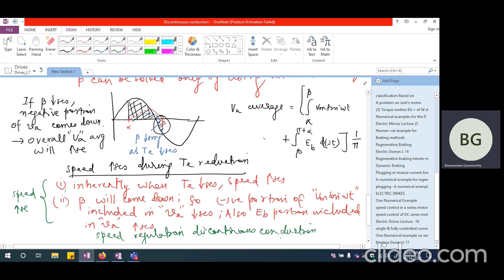So if I am going to reduce the torque from 5 Newton meter to 4 Newton meter in continuous conduction, whereas in discontinuous conduction, I am doing the same reduction in torque from 5 Newton meter to 4 Newton meter, the speed increase in continuous conduction may be 100 RPM, whereas the speed increase in discontinuous conduction may be 150 RPM. So speed regulation in discontinuous conduction is more. So this is not really a good thing.